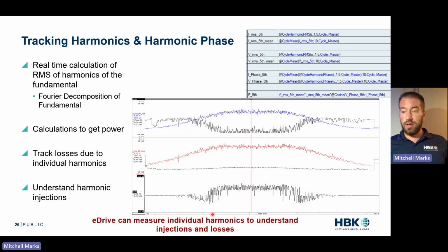I've alluded to this a few times now, and I probably should have included it. But if you're running at 1 kilohertz and you have a 3 kilohertz filter, you are missing your fifth harmonic. And your fifth harmonic carries power, carries negative power. So you're actually going to see a higher value than what you actually get. So if you have your filter set high enough, you can start to do things like looking at your harmonic RMS and phase. And this is an equation we offer in the eDrive system.